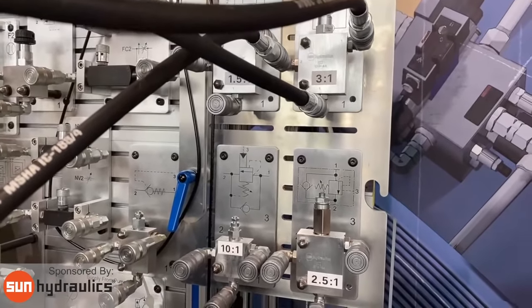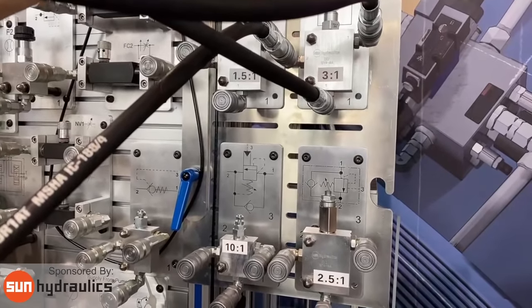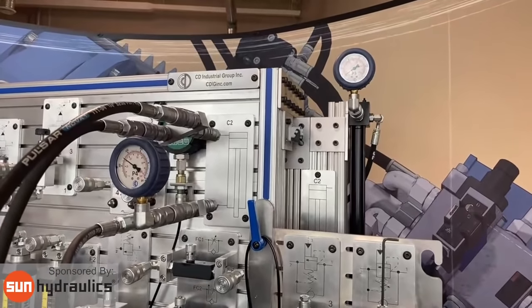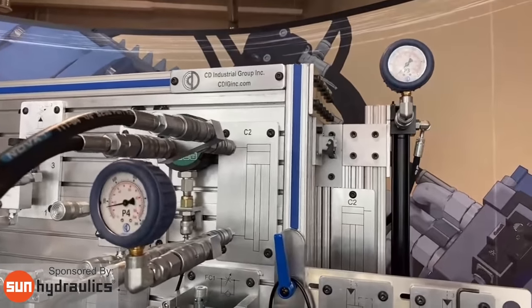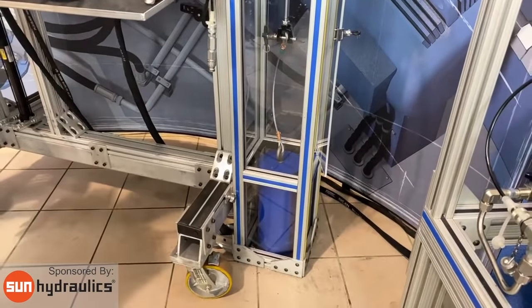Although in our simulation we show that the differential changes, which it does, but we won't see an action. So then people say, well, I should have turned it the other way. Well, now we don't even know where we're at. So it's very hard to set with pressure gauges on the cylinder in the live machine. Very, very challenging. Not really possible to do that, nor safe. Correct.